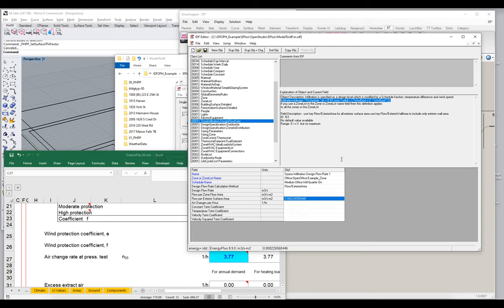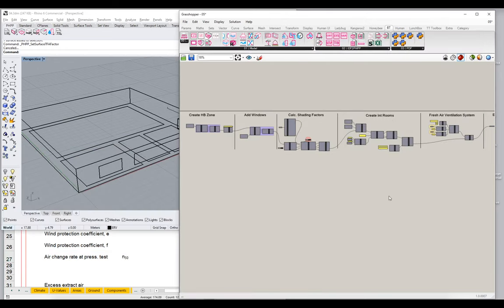For our project, we want to override all of this and set our value much more carefully. If we want alignment between EnergyPlus and the PHPP — if we're trying to get a mirror version of the model — we're going to have to simplify the EnergyPlus, override the variation in leakage, and apply a constant schedule for the whole season so the EnergyPlus model more closely matches the PHPP results. Maybe you don't want to; maybe you want EnergyPlus to be EnergyPlus and the PHPP to be the PHPP, and that's fine. We're just going to show the method here — you can choose to use it or not.